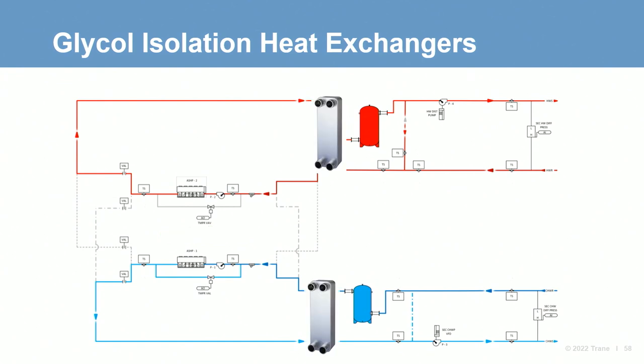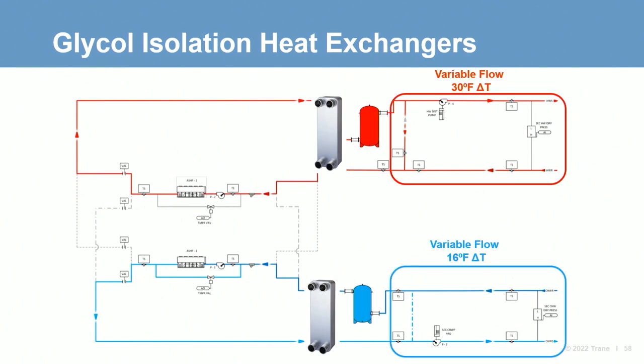strategies. Fluid isolation heat exchangers can be properly applied between the production and either or both distribution loops if the design calls for differing fluids in the distribution loops. The designer must take into consideration that below freezing temperature may enter a heat exchanger from the production loop during system changeover or a defrost cycle and take the appropriate design precautions. We have established the four-pipe distribution system featuring separate heating and cooling loops.